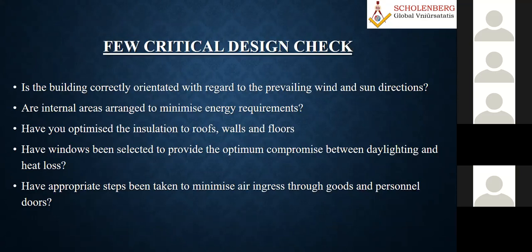Some of the critical design checks: how do you do it? Is the building correctly oriented with regard to the prevailing wind and sun direction at the design stage itself? As an HVAC engineer, you should always have the data to check whether it is meeting the local building code, because architects also follow it, but you can always check with that. Are the areas arranged to minimize energy requirements? Some places the architect looks at the flow from a different angle, but when you go through the areas, you may always have a suggestion on the flow and arrangement of the areas. This is again the integrated design I mentioned on the first slide: at every stage of communication, you have to interact with each end user.